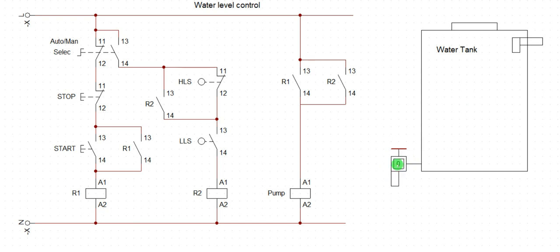Now, when the discharge starts taking water out of the tank and it comes to the lower limit switch, the pump is going to be activated to fill the water again. When the water fills to the top, to the preset limit of the level here, another switch here will shut it down. This is a float switch, this is another float switch. This is the lower level switch, this is the higher level switch. So just understand the water movement in the tank.